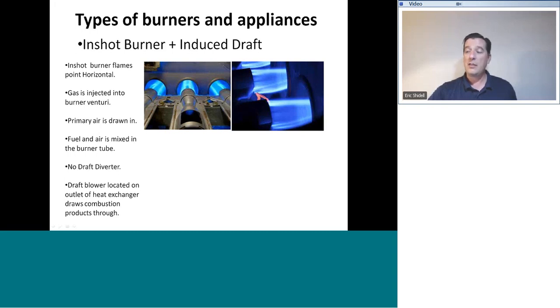In a way, these are designed and built so that you cannot really screw up the primary air mixture on these burners. You may notice that most of these burners, like the one in the picture here, do not even have an adjustment of the air opening for that reason. It is specifically sized to be appropriate within a wide fluctuating range of gas pressures. It will always give you the right ratio of fuel to air. Pretty nice, pretty neat.